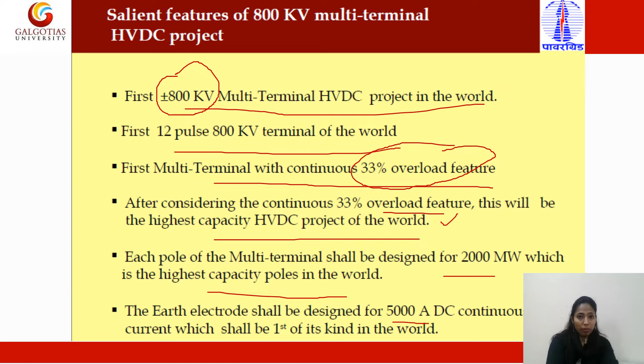So this is the first project in the world which is multi-terminal, working on plus minus 800 kV, and the overload capacity is also 33%. Each pole of the multi-terminal shall be designed for 2000 megawatt, which is the highest capacity pole in the world. Earth electrode shall be designed for 5000 ampere, so it shall be the first of its kind in the world. This project is very important in India.